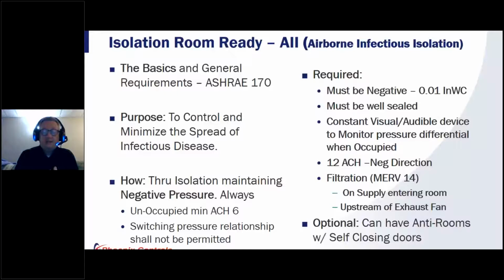Again, we need to maintain 12 air changes, negative direction while occupied, right? And any kind of filtration on the supply must be at least a MERV 14. Obviously that's a minimum, and it can be supplied higher if needed, MERV 17 or MERV 19 or HEPA. Upstream on the exhaust fan, it's recommended to have filtration as well, right? Now, in the States, isolation rooms can have ante-rooms with self-closing doors that does tend to make things a little bit more complicated, but that's something that we can certainly help with.